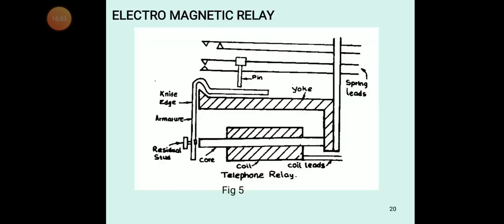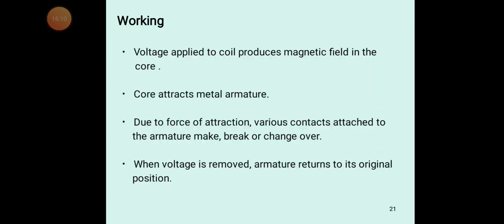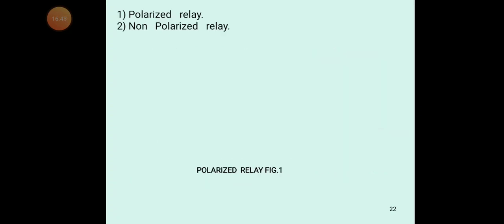The working of the electromagnetic relay: voltage applied to the coil produces a magnetic field in the core. The core attracts the metal armature. Due to the force of attraction, various contacts attached to the armature make, break, or change over. When voltage is removed, the armature returns to its original position. When voltage is not removed, it remains energized and acts as a magnet.